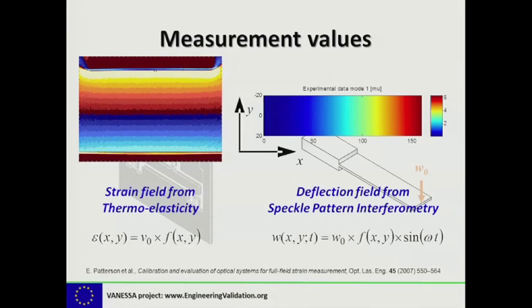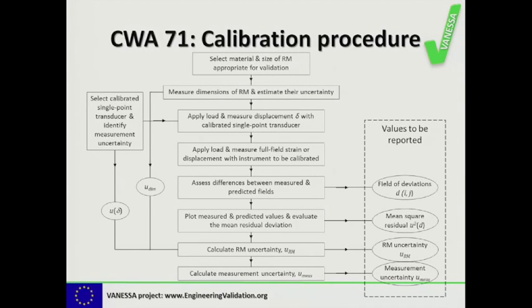This is how the measurement values would look. On the left you see a strain field from a thermo-elastic measurement; on the right you see a deflection field pattern in dynamic loading from a speckle pattern interferometer. The strain and displacement values are quite simple and can be described by a simple function f(x,y) given analytically. Comparing these measured values to the reference values sets the reference material in relation to your measurements and gives you the calibration of your instrument. This flowchart is described in the CWA — the CEN Workshop Agreement 71 — which was part of the Vanessa project.